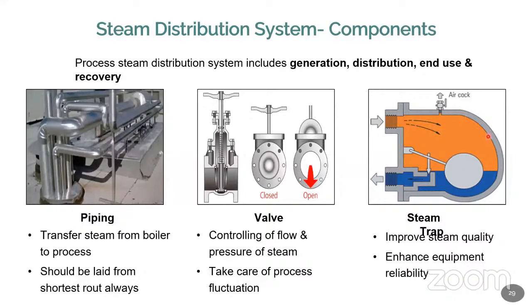Okay. Now this is a very simple example where we have a steam line. When water is available, there is a small floating ball. When the water level is higher, the floating ball automatically opens and the water comes out. Once the water has come out, it starts closing. Right. So when water is again available, it will start moving in this direction, open the valve, and the water will go out. So this is mainly used for enhancing the quality of the steam.